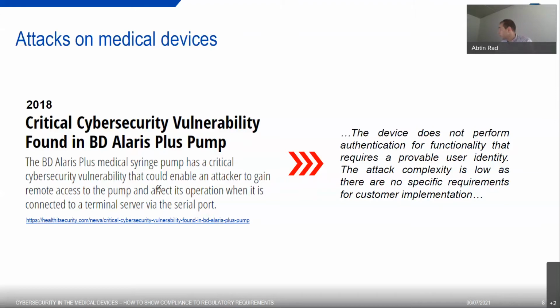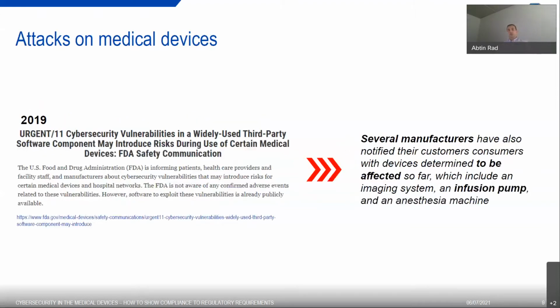If you look into the last year, 2019, there was an interesting vulnerability identified by the FDA, where the FDA issued a safety communication on a software component. VxWorks is the name of it, and this was very often used in medical devices and in vitro diagnostic devices. The vulnerability actually could allow hackers to remotely control a medical device.